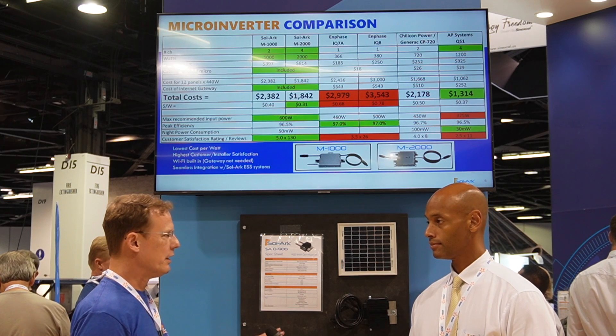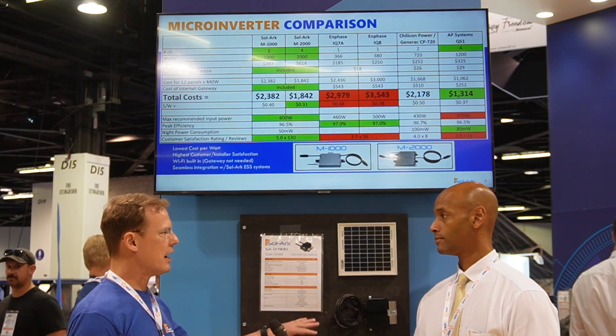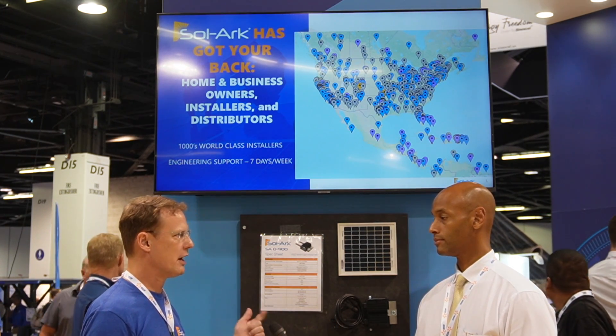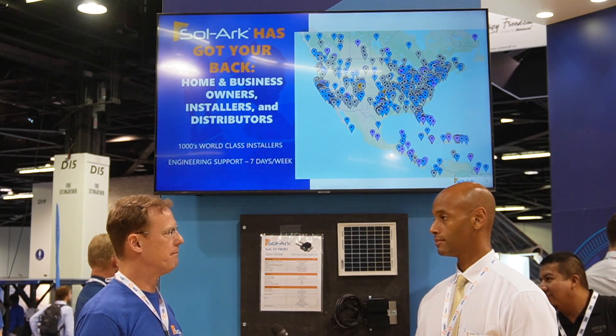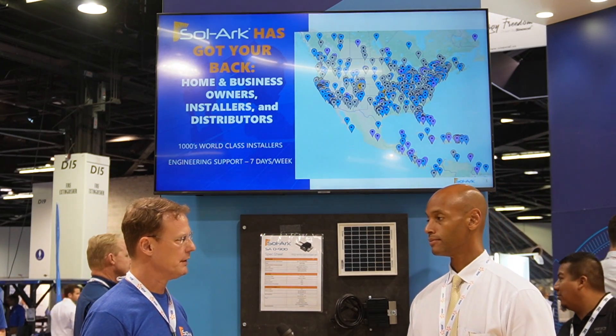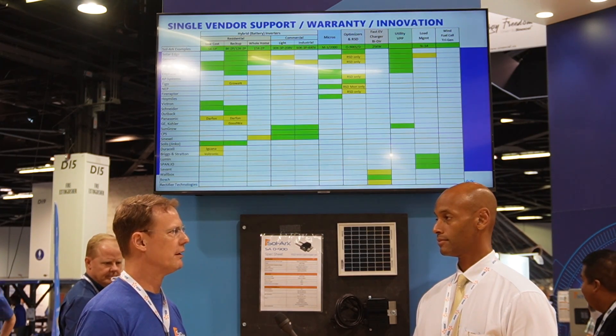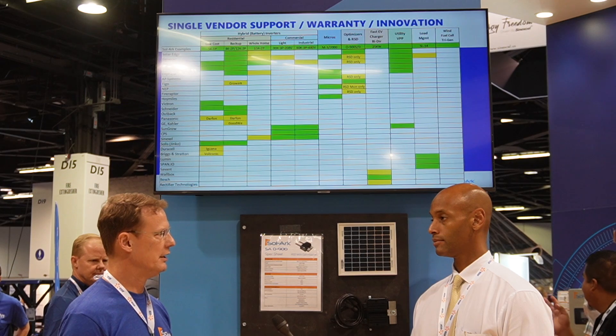The difference between our optimizer and other optimizers is that it's not operating in optimizer mode all the time. Most optimizers — microinverters and optimizers — they're converting power all the time, and that's an efficiency problem. What we did is we only convert when there's shading and it needs to optimize. Therefore, the rest of the time it consumes very, very little power — much more efficient, much more reliable, and producing less heat.